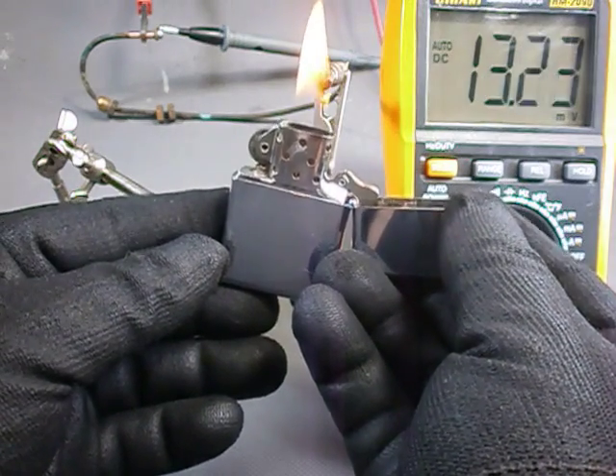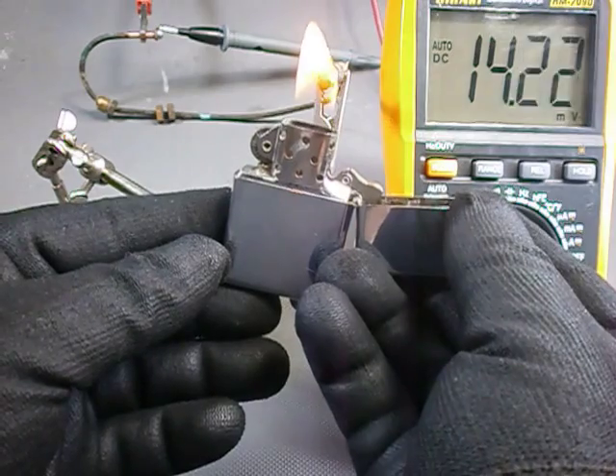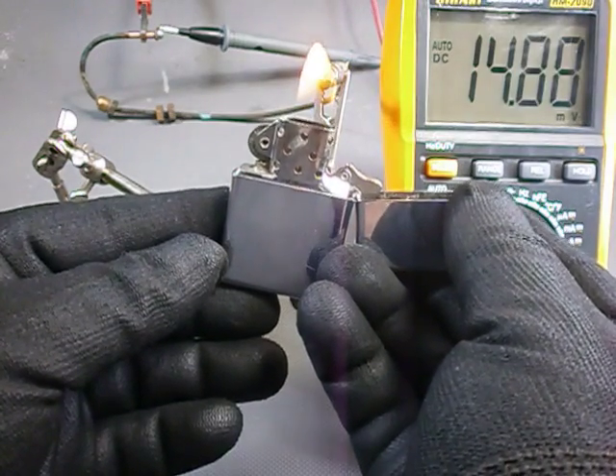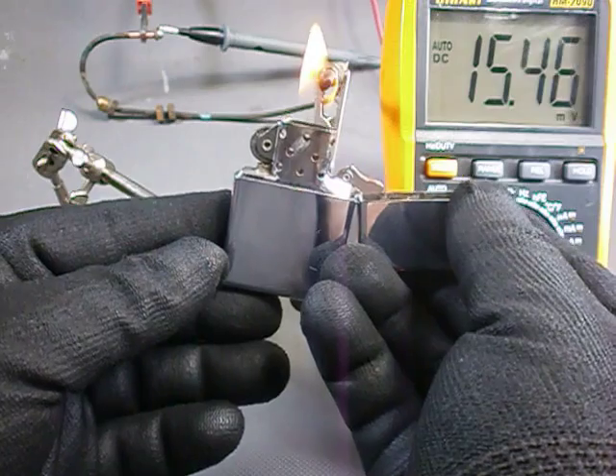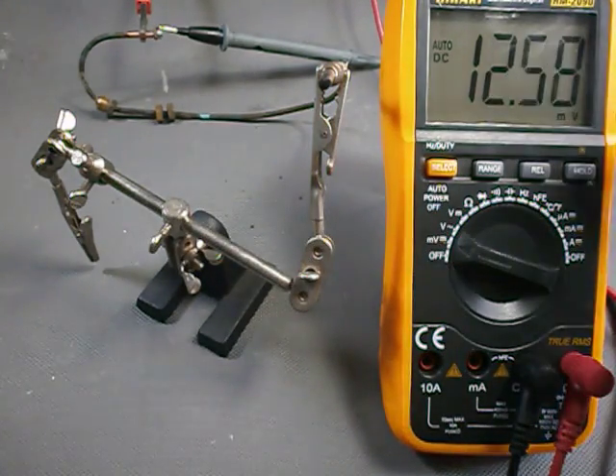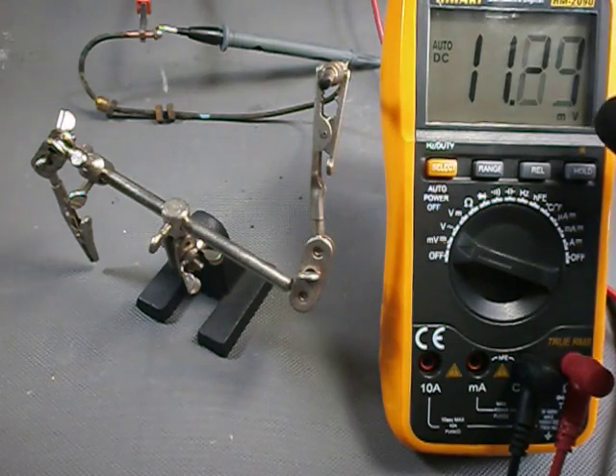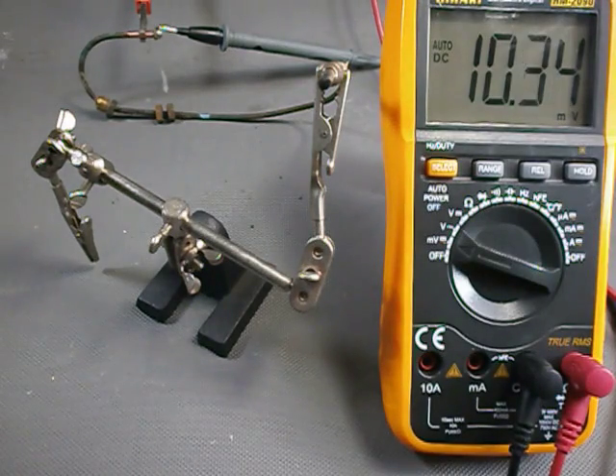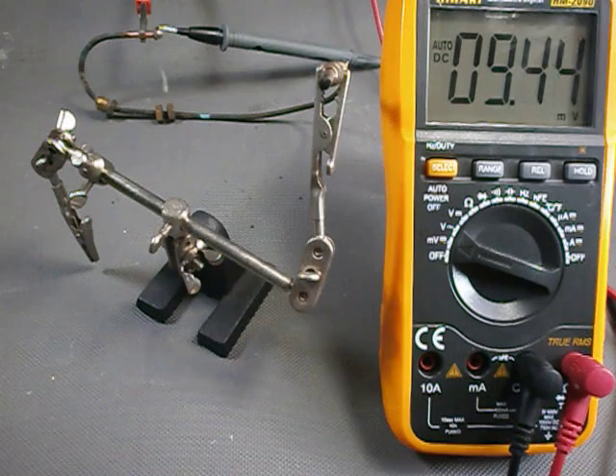After around 15 or 20 seconds it stabilizes around 15 millivolts. After we remove the flame the voltage starts to decrease also instantaneously. It takes more than one minute for the voltage to go under one millivolt. Well it seems that our thermocouple is okay.